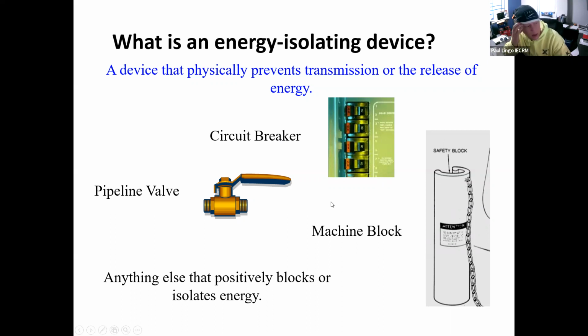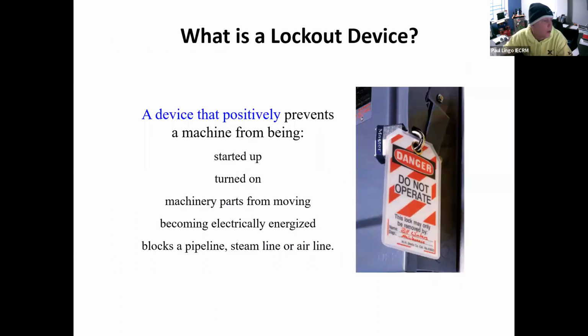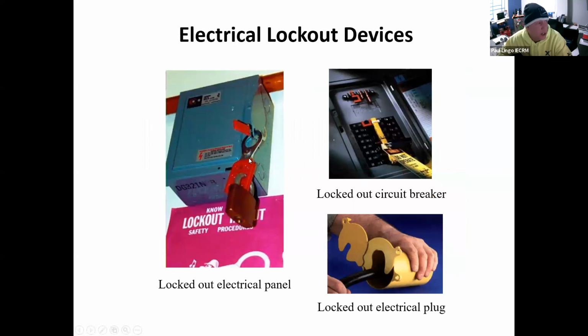Anything that can positively block or isolate energy, they make guards for, and lockout tagout devices for. So you've got your standard disconnect here, right? We've all seen these. You've got stuff that can isolate individual circuits, as well as lock that whole can out. Up here at the very top, you can lock that whole can out, eliminate the energy source, test it downstream, and then you know not only what the hazard is or isn't, you know the PPE you need to don to perform that work.